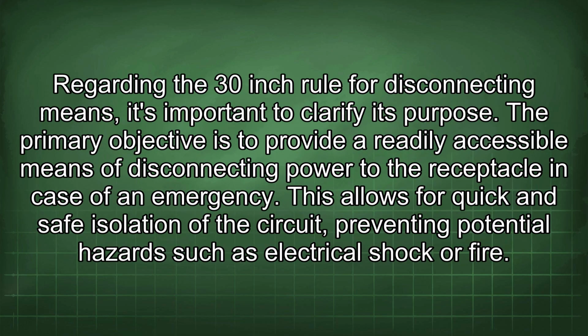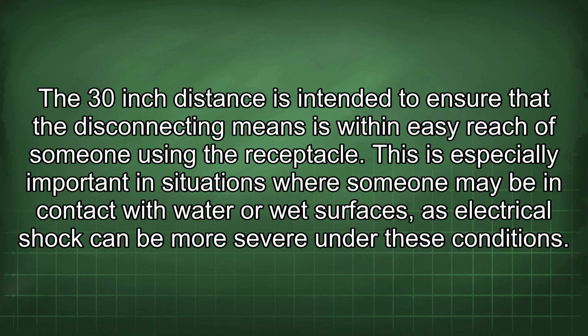Regarding the 30-inch rule for disconnecting means, it's important to clarify its purpose. The primary objective is to provide a readily accessible means of disconnecting power to the receptacle in case of an emergency. This allows for quick and safe isolation of the circuit, preventing potential hazards such as electrical shock or fire. The 30-inch distance is intended to ensure that the disconnecting means is within easy reach of someone using the receptacle.